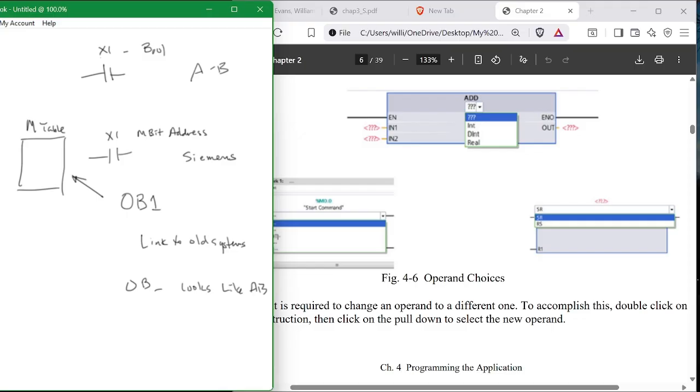So I can have a coil that's using a bit of M-bit territory for one thing, and then I can have a coil someplace else that's using that same bit for something else. Now, who wins? Last guy wins. Because as your program executes down through it, you've got this, and this, and this. The last time you use that bit with that name is the one that wins. So if you double use a bit using the same M-bit reference, it joyously doesn't do the first one, but will do the second one.